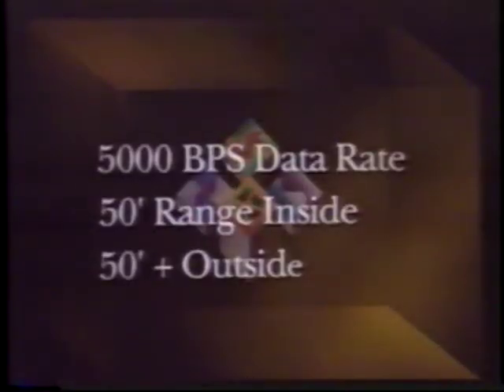The LonWorks wireless RF transceiver is a compact, cost-effective solution that can operate from batteries. It provides a 5,000 bit per second data rate, a 50-foot range inside buildings, and more outside. LonWorks transceivers work transparently with each other because all messages, no matter which communications media are used, are in LonTalk. So a LonWorks network can be assembled from any combination of communications media, served by any LonWorks transceivers. Powerline, RF, and twisted pair transceivers will first be available as evaluation modules that work in conjunction with the LonBuilder Developers Workbench.